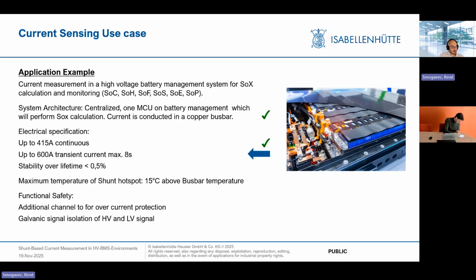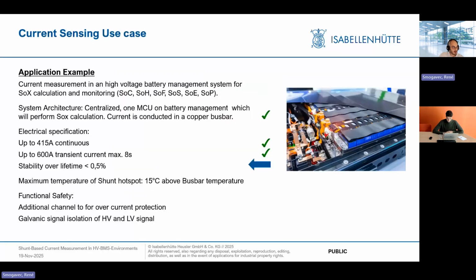So we also have a transient current, 600 amps, 8 seconds. If we go back to the datasheet, it's also listed there. So if you check 10 seconds, it's below 10. You have 600 and 800 amps, so it still is enough to use the 100 microohm. And obviously you try to stick with the higher ohmic one because of the higher voltage drop you can achieve with this. So less noise in the process of signal processing. Stability over lifetime is also all on the first page of the shunt datasheet. So it's specified with 0.5, even though it's very conservatively chosen. If you see our laboratory test reports, we usually go way below that. So just ask us, we can give you an external copy of that.